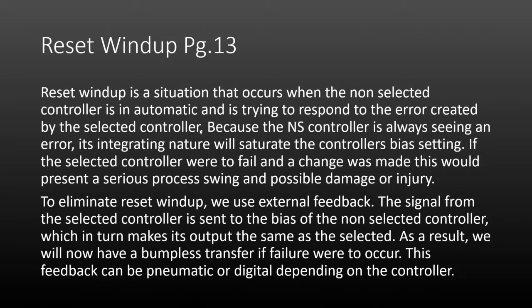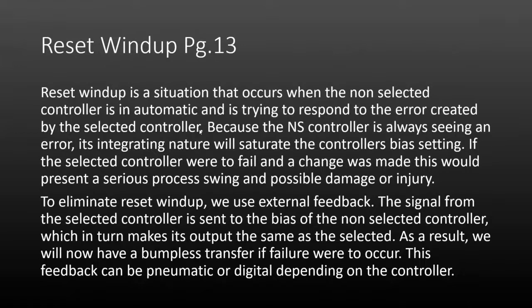Its integrating nature is going to start to saturate the controller's bias setting. The controller output goes up, up, up to 100% and then keeps saturating past 100% — we call that value the reset windup value — and it'll continue until it gets feedback telling it to go the other way. It's very bad because that reset windup is above and beyond the 100% range of our normal operating system.